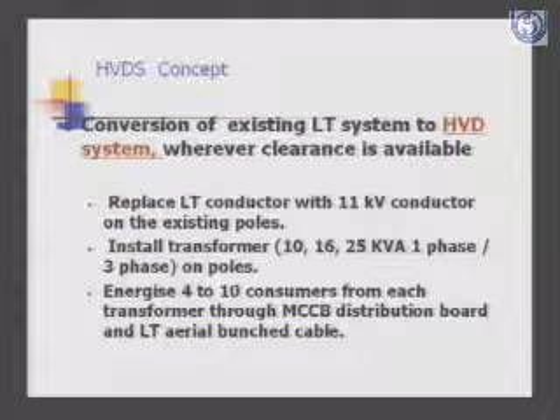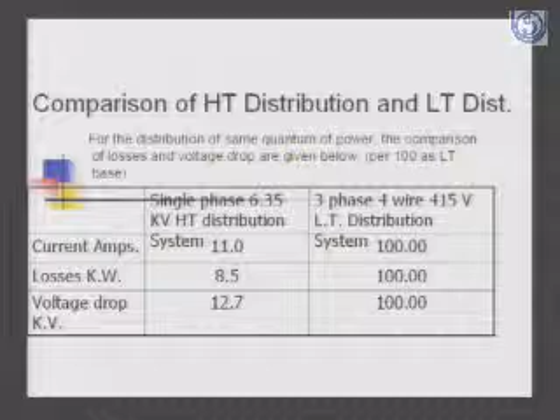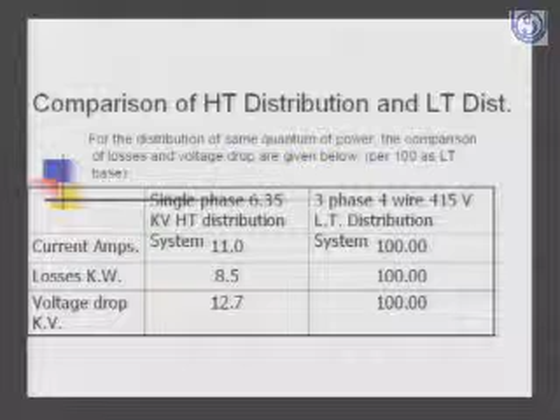If you compare the high voltage distribution system and the low voltage distribution system, if the current in the LT distribution system is 100 amperes, then the current in the high voltage distribution system is going to be 11 amperes. If the losses are 100 kilowatt in the LT distribution system, they are likely to reduce to 8.5 kilowatt in the high voltage distribution system. If the voltage drop is, say, 100 volts in the low voltage distribution system, it's only going to be 12.7 volts in the high voltage distribution system.